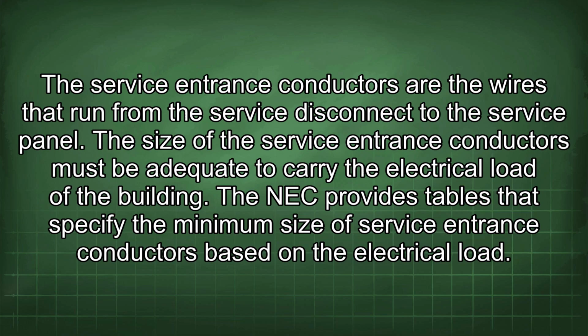The service entrance conductors are the wires that run from the service disconnect to the service panel. The size of the service entrance conductors must be adequate to carry the electrical load of the building. The NEC provides tables that specify the minimum size of service entrance conductors based on the electrical load.